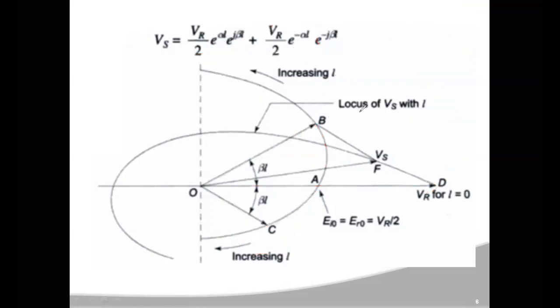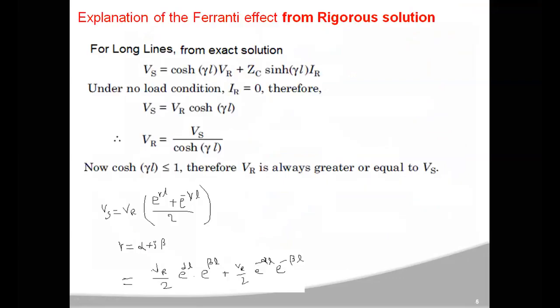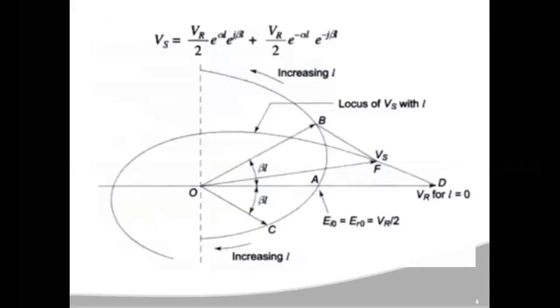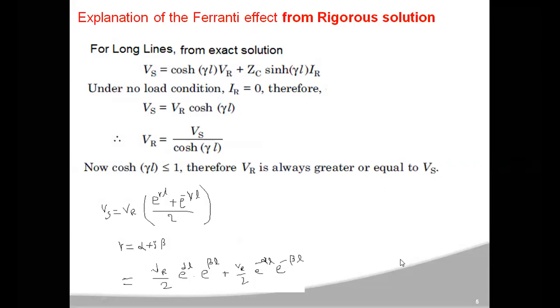The sum of the two vectors OB and OC will equal the total sending end voltage. From the vector diagram, you can see that the magnitude of VS will be less than the magnitude of VR. That means receiving end voltage is greater than sending end voltage — this effect is called the Ferranti effect. This is how you can explain the Ferranti effect from the rigorous solution.